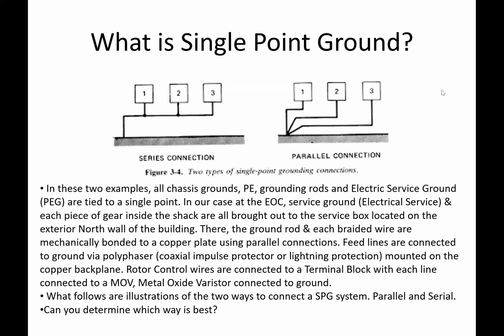I know a lot of you have seen that box outside. It's mounted to the building, and that's where all the grounding business takes place. There, the ground rod and each braided wire are mechanically bonded to a copper plate using parallel connections. Feed lines are connected to ground by a polyphaser, a brand name, meaning a coaxial impulse protector or lightning protection, mounted on the copper backplane. The rotor control wires are connected to a terminal block, with each line connected to an MOV, a metal oxide varistor, connected to ground.